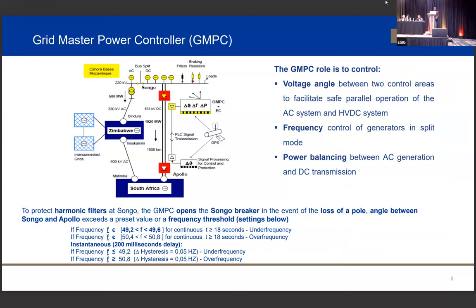Okay, between us, South Africa at the bottom there, we have what we call the Grid Master Power Controller, GMPC. The role of the GMPC is to control voltage between two control areas to facilitate safe parallel operation of the AC and the DC system. Also under split mode, it controls the frequency. Normally when the two areas get split via the AC, the controller takes over and controls frequency on that element. Also, it balances the power between the AC side and the DC side of the transmission.